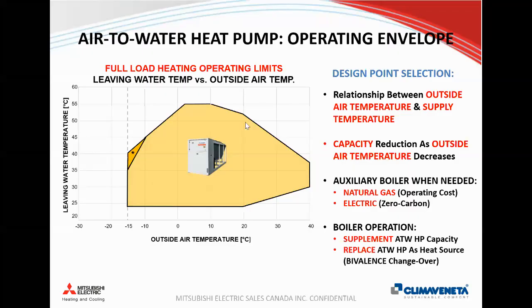So when you approach any manufacturer that offers these heat pumps, whenever they provide you a selection based off your design conditions, so when you tell them the water temperature and the air temperature that you want to run the heat pump down to, they'll provide you a selection that reflects the available capacity at that point in time. But it's important to remember that as it gets warmer, or if you differ from the nominal conditions, your capacity will change. So it's important to understand that and review in the product literature accordingly.